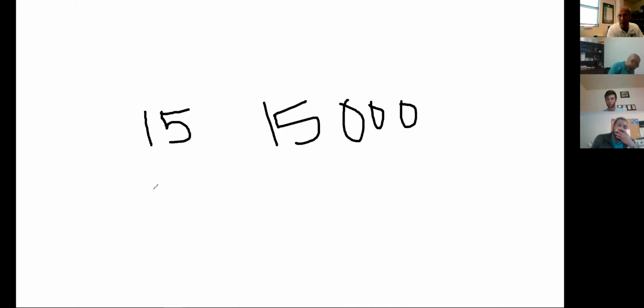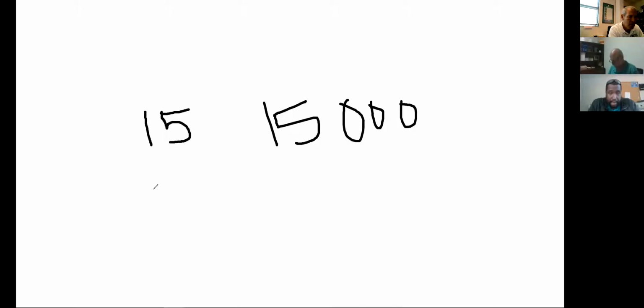And once we did the calculation of the 2.6%, our answer is still in watts: 14,565. I need it converted back to kVA. So at the 14,565, at the ending 5, I need to move over three places: 10, 100, 1,000. You should have 14.565. You've now converted it back to kVA.